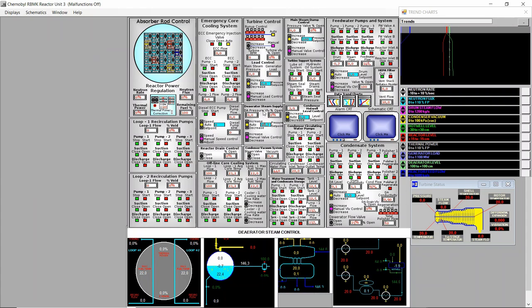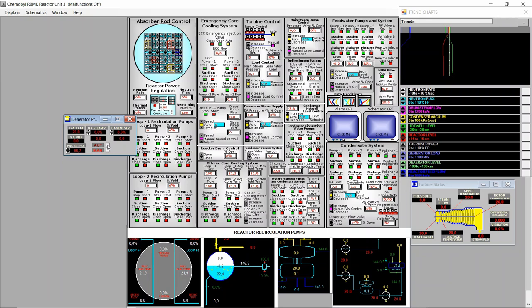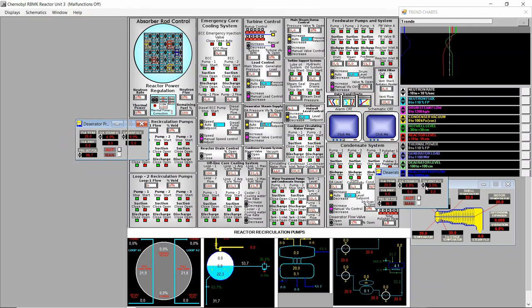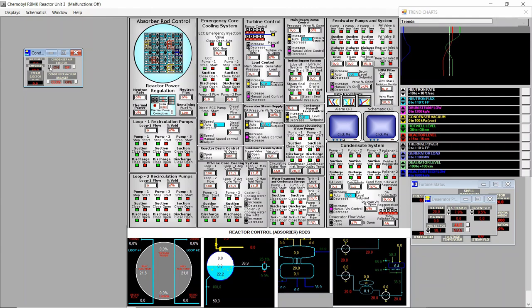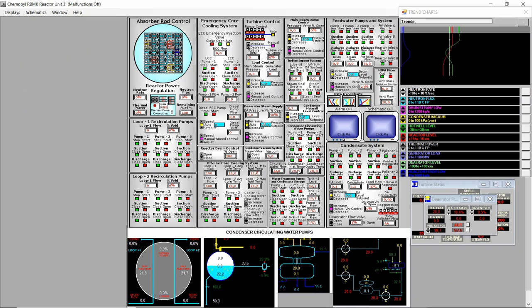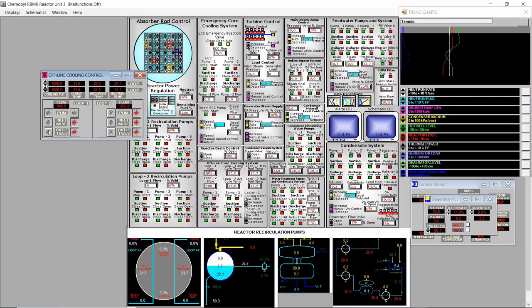We go now to the deaerator system. I will set it into auto, and we need to open the deaerator vent valve to 50 percent, but I will just open to 10 percent now and leave it in front of the turbine so I don't forget. For the condenser vacuum system, we switch on the condenser air ejector — it won't light on until we have enough pressure. Then we can shut down the off-line cooling systems, which are going green.